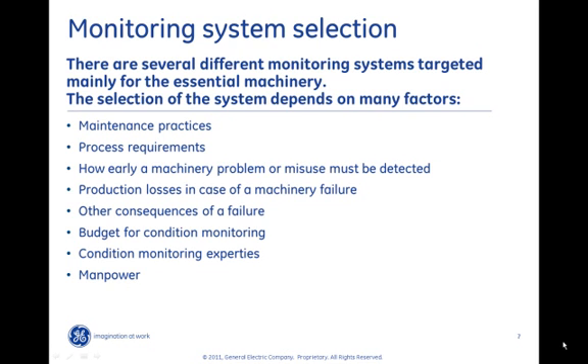Process plays an important role here. If you have a plant operating 24/7 you will need a different condition monitoring solution than if you are running your plant eight hours a day, five days a week. It all falls into defining the criticality of a single machine for the production. In a perfect world, a criticality analysis for the whole plant has been performed and maintenance practices and condition monitoring operations are selected accordingly for each asset. How early a machine problem needs to be detected matters greatly — different machine problems have very different PF curves. It's very important that the monitoring system is selected firstly to be capable of detecting all expected failures early enough and also to track failure development. In cases where the PF interval is very short, an online monitoring system with protection functionality is often required.